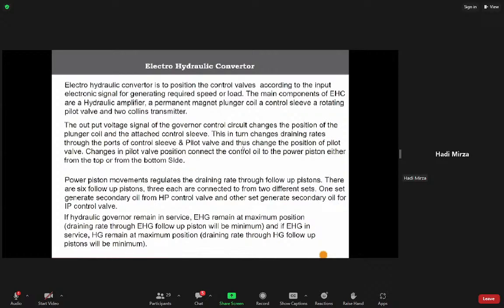The electrohydraulic converter positions the control valve according to the input signal, for generating the required speed and load. The main components of the EHC and hydraulic amplifier are a permanent magnet plunger coil and control sleeve, a rotating pilot valve, and two Collins transmitters. These are the main parts of the EHC. The output voltage signal of the governor control circuit changes the position of the plunger coil and the attached control sleeve.